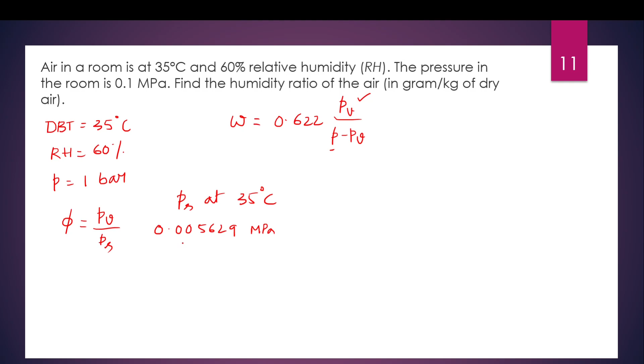So the omega formula is 0.622 PV by (P minus PV). Here PV is not given, we have to find PV first. So we know that phi or RH is equal to PV by PS. So if you take PS at 35 degrees centigrade, at 35 the saturation pressure is 0.005629 MPa, which is equal to 0.05629 bar. The steam tables I am using give values in megapascals, that is why I have converted into bar.